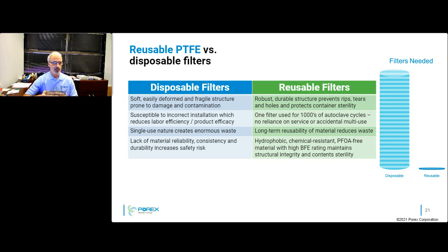Disposable single-use nature creates an enormous amount of waste versus the reusable, which reduces material waste. And disposable filters' lack of material reliability, consistency, and durability increases safety risk. There are numerous brands out there, and sometimes you don't really know what you're getting if you're using off brands. The reusable filter is extremely hydrophobic. Water does not penetrate it. It's super chemical resistant. It's PFOA free. It has extremely high BFE ratings, like I mentioned, a 99.999% BFE rating, and structurally it's extremely robust.